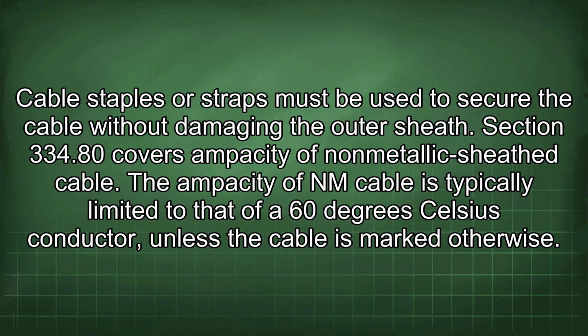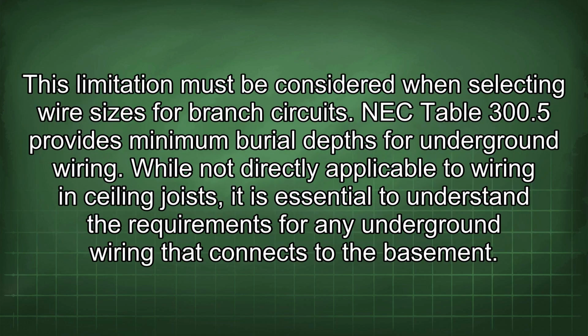Section 334.80 covers ampacity of non-metallic sheath cable. The ampacity of NM cable is typically limited to that of a 60 degrees Celsius conductor, unless the cable is marked otherwise. This limitation must be considered when selecting wire sizes for branch circuits.